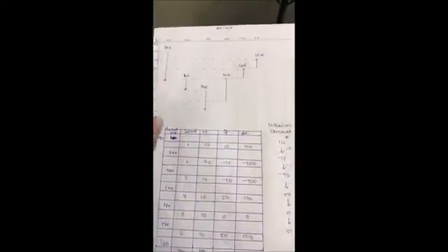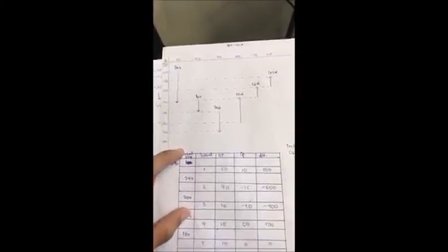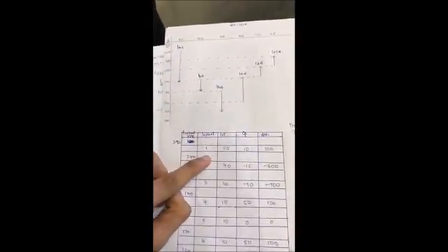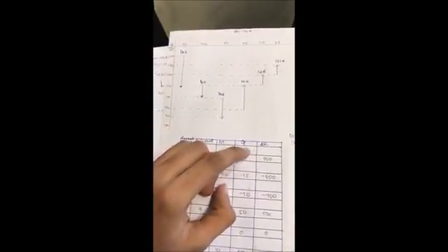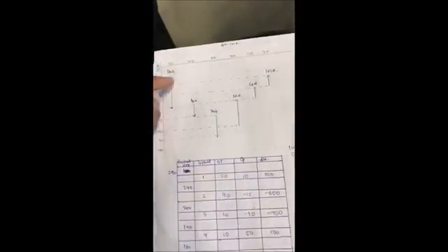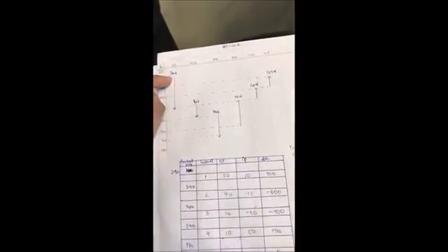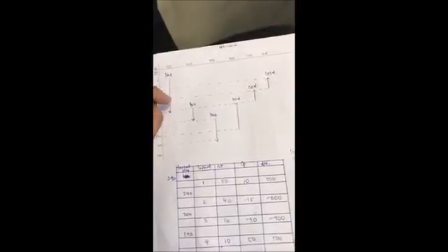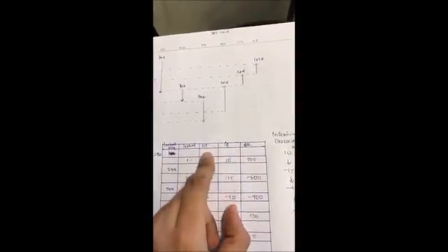The next step after you have done this is to determine the interval. For example, the first interval between 290 and 240 is the first interval. There is a delta T of 50, 290 minus 240. And how do you determine the Cp value? By looking at the interval here. In this particular interval, there's only one stream present, which is this first stream with a Cp of 10. Then you find out the delta H, which is Cp multiplied by delta T.